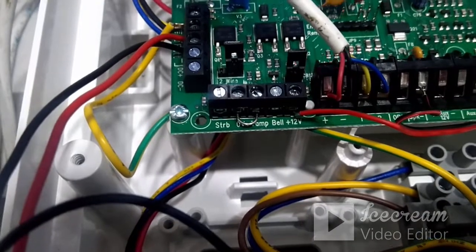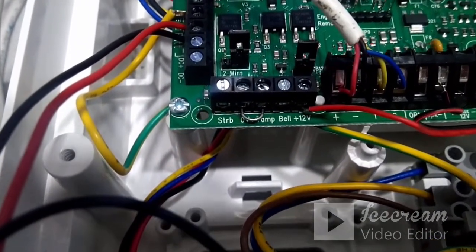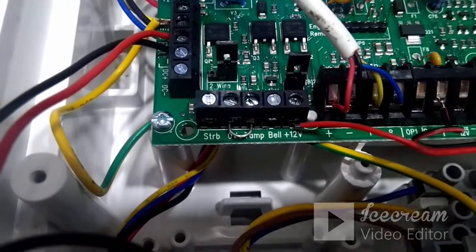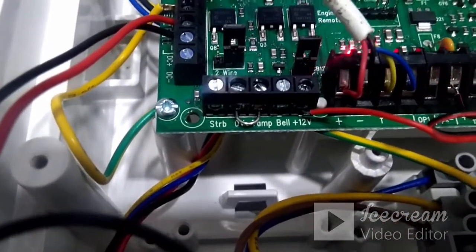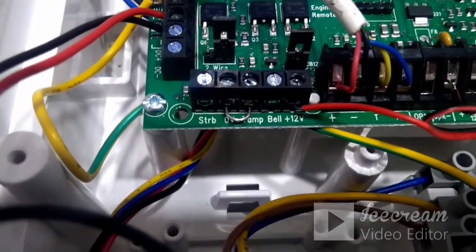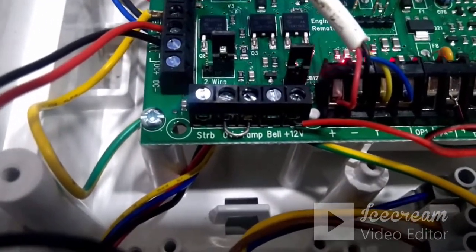On the panel's sounder connection there are five pins: plus 12V, bell, tamp, 0V, and strobe. If the sounder is a Texecom sounder, the same five pins are available on the sounder side as well. What you need to do is remove the jumper shorted between 0V and the tamp terminal, then connect all five terminals with the sounder. This is how you connect a Texecom sounder with this panel.